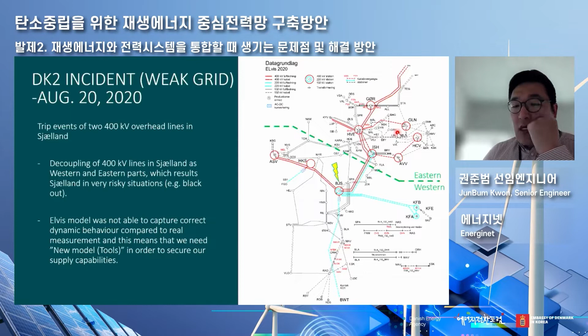Energinet is replacing a lot of old cables or lines, and when new offshore power or HVDC is added to the grid, we do a lot of simulation and analysis. The important thing when simulating is whether it's really close enough to the actual case. We have used a lot of RMS databases, and Energinet is proud to have a relatively advanced RMS system, but the system that had the accident was a weak grid, so we could not do simulation based on RMS.